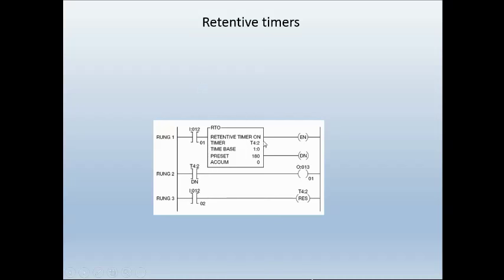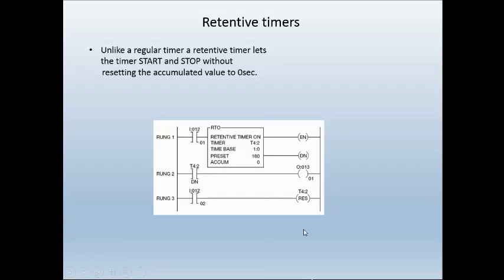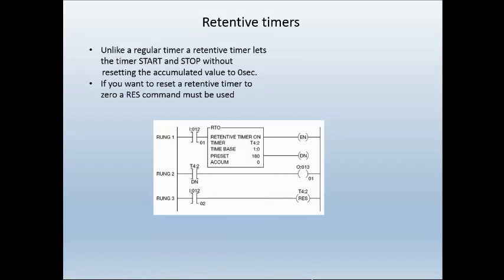We do have the option of retentive timers — they're an RTO instruction. These timers do not reset when the logic in front of them has been removed. They're very similar to the other timers, except the accumulated value will not go back to zero if the logic in front is false. The only way to reset the RTO timers is to use the reset command. So if the reset contact becomes true, it will reset that timer — T4:2 is the timer address — and set the accumulated value back to zero. And that's about all I have for timers for you.